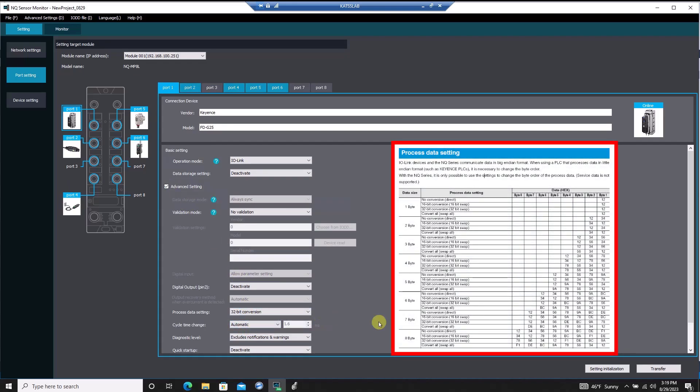The other way to do this is by using our add-on instruction for writing messages to the NQ. I'll start by importing the write AOI and add it into my main routine. I'll need to create new tags for each field of the instructions. The important fields here are the REQ tag, which is just a Boolean I need to toggle to initiate the message, and the write data tag, which is where I can specify the contents of a message or command that I'm giving to my IO-Link sensor. The port number field lets me specify to which port on the NQ to direct my message. The IO-Link index field lets us select which parameter of an IO-Link sensor to adjust via service data.